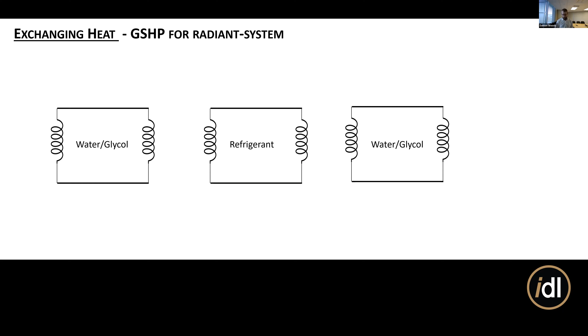So looking at what that might be like in a building, we've got buried coils out here, our heat exchanger to our refrigerant, and a separate heat exchanger here to our hydronic system, which might be in some PEX tubing within the floor. You can also do direct burial of the refrigerant line and have all of this as one refrigerant instead of having a heat exchanger. Haven't seen that as much in Idaho. Perhaps my experience is just limited, but traditionally what I see come across, at least in terms of design reviews, is water and glycol, and then a heat exchanger to the refrigerant that is simply contained within the heat pump.